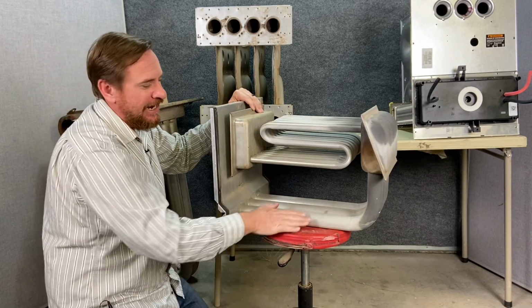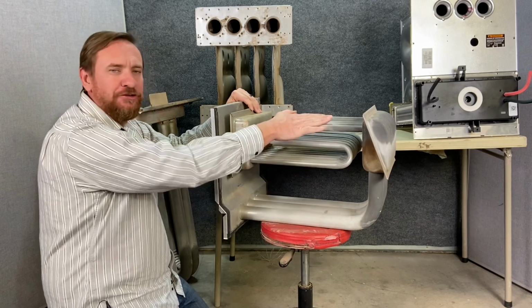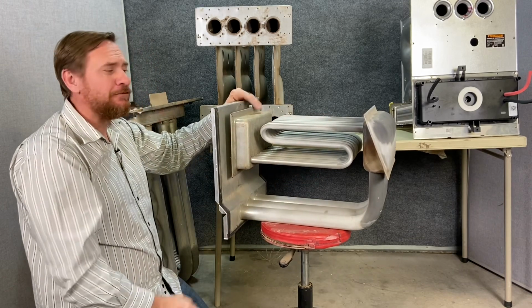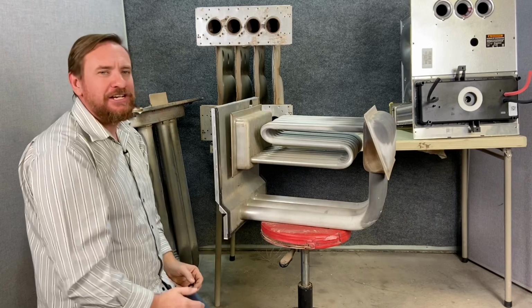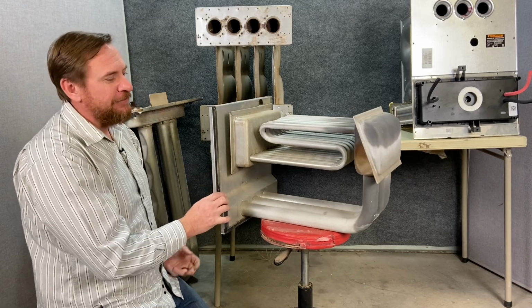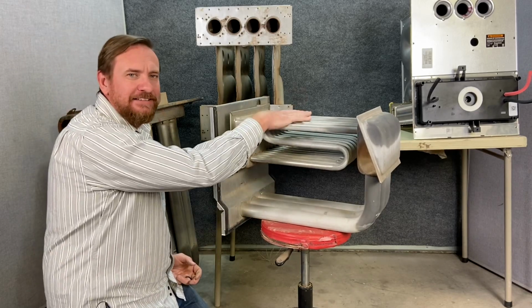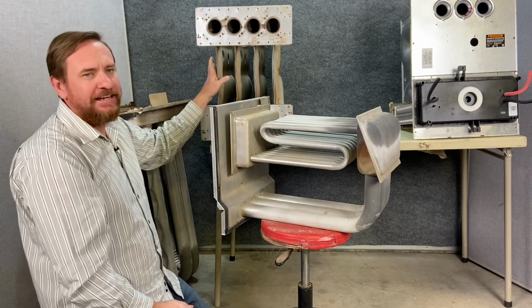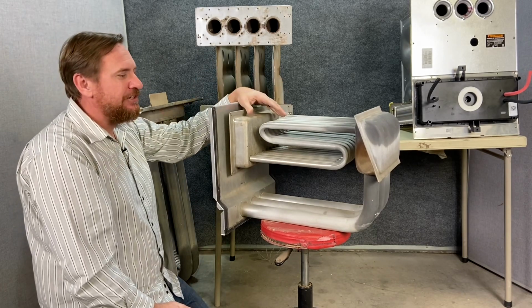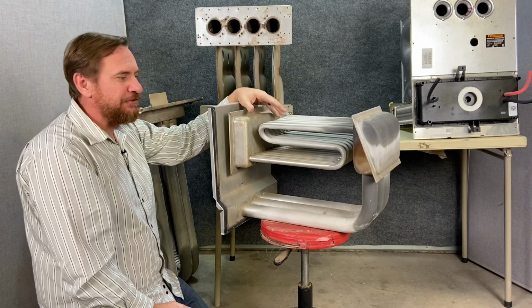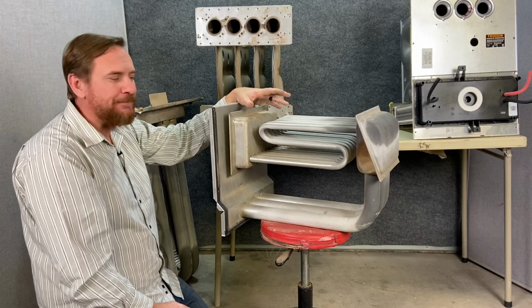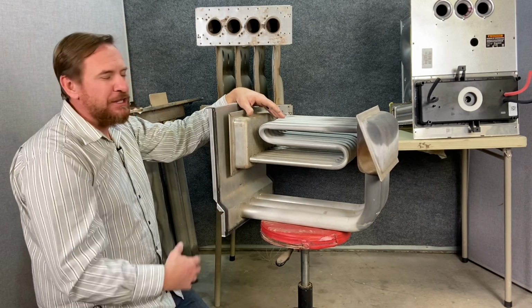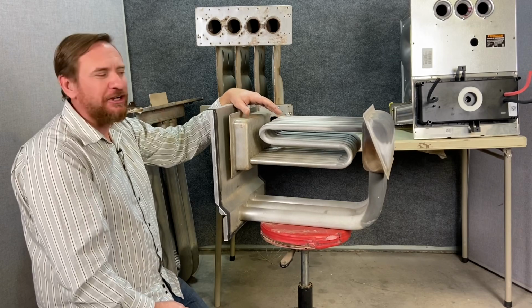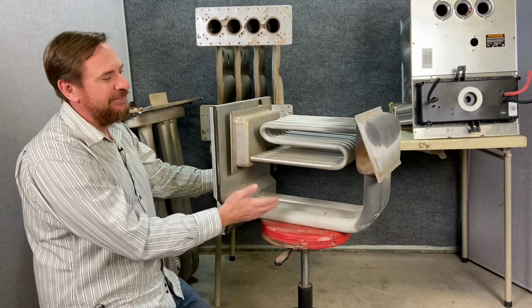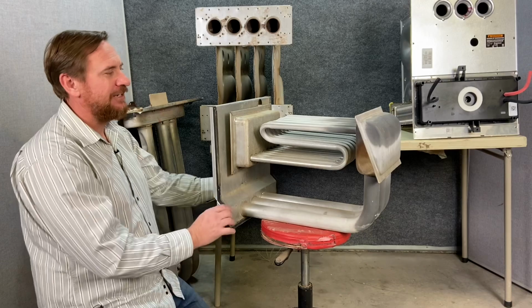The idea is the air has to travel between all of these tubes so we get the majority of the heat, or as much heat as we can, out of this heat exchanger. So there's a lot of different preferences between people liking this style furnace and this style furnace for the heat exchanger, but the engineers and manufacturers have all gone through tests and decided what works best for them. As far as which one you prefer, there will always and forever be an ongoing argument over brands. But this is a typical 80% efficiency gas furnace.